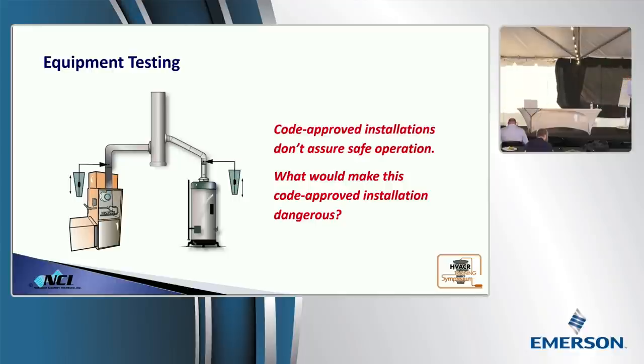But you may say, wait a minute, doesn't that furnace have a pressure switch in it? What happens to the pressure switch if there's a relief opening? It thinks everything's great. It has no way of knowing that the flue's restricted. This is what we call the most dangerous installation allowed by code. You guys run into this installation a lot? All the time. You run into occasional pilot outages on them.